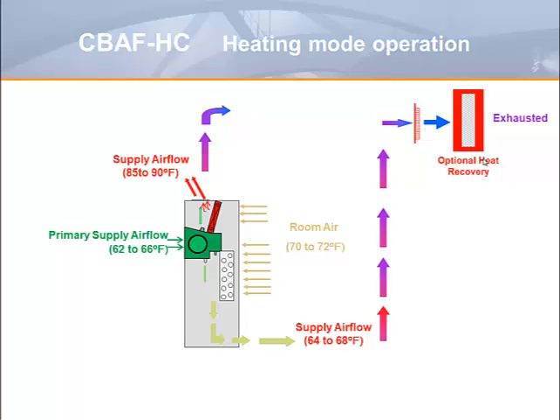This slide illustrates the operation in a heating mode. Primary air is delivered through the nozzles, which induces room air through the upper coil, which is heated and delivered through the grill on the top to satisfy the heating conditions in the space. At the same time, the primary air delivered through the nozzles in the coil below mixes with the room air and delivers cool air to satisfy the sensible load conditions in the space. The resultant air delivery to the space is a displacement type mixture of primary and recirculated air at 62 to 68 degrees.